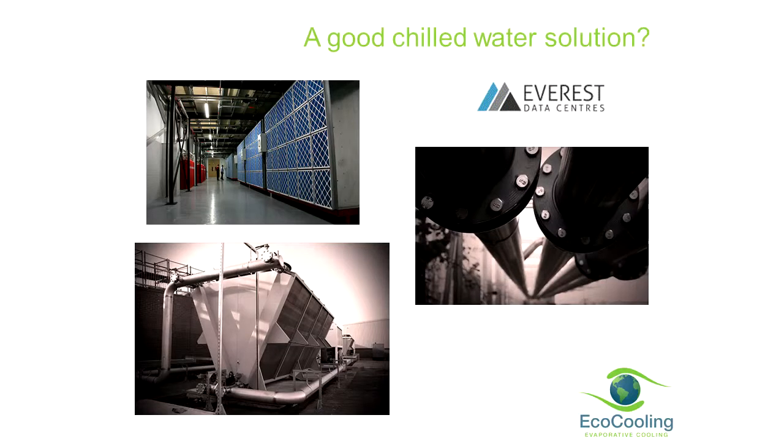A lot of people are very dismissive of chilled water systems. I come across some very, very efficient systems. If you're designing a data center, and you give due attention to efficient design of the plant and equipment, it does end up being quite big, not necessarily expensive. But if you're designing low energy airflow systems, low energy pump systems, maximizing your free cooling, introducing adiabatic cooling into your dry chillers, then, for instance, down at Everest, down in Reading, they are seeing a PUE of well less than 1.1 on a chilled water system. Very impressive. But down there, they started from scratch and designed everything themselves with this in mind. Not cheap, it's about efficient and low cost.